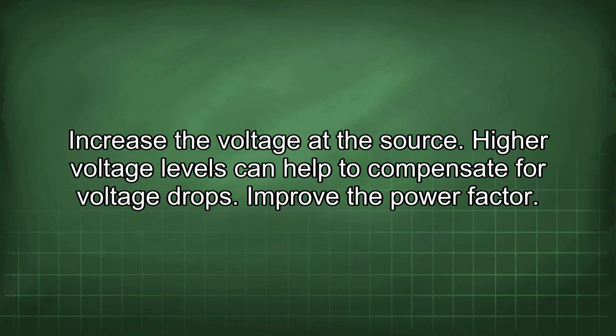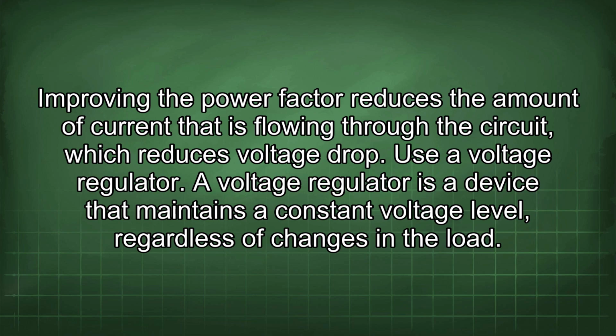Improve the power factor. Improving the power factor reduces the amount of current that is flowing through the circuit, which reduces voltage drop. Use a voltage regulator. A voltage regulator is a device that maintains a constant voltage level, regardless of changes in the load.